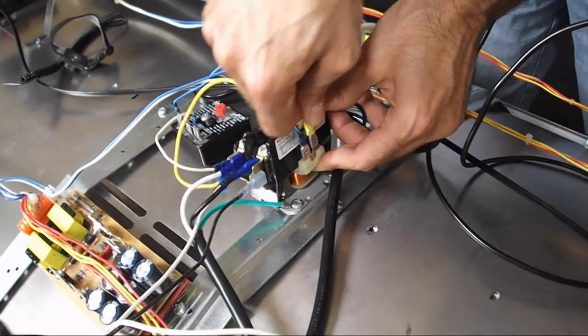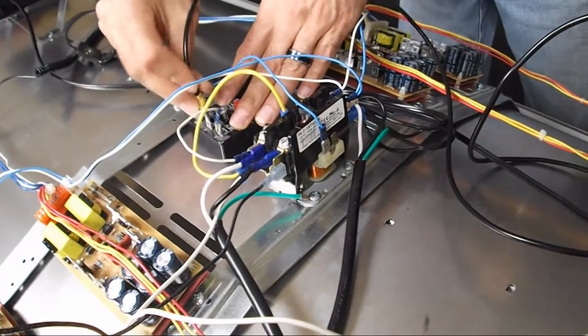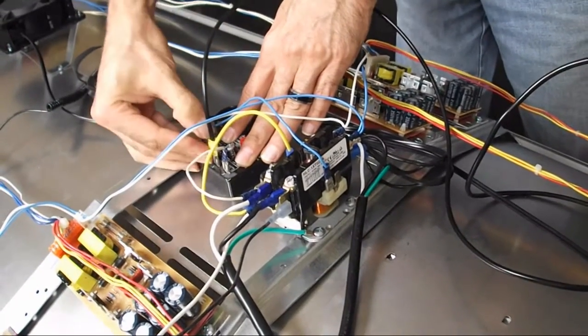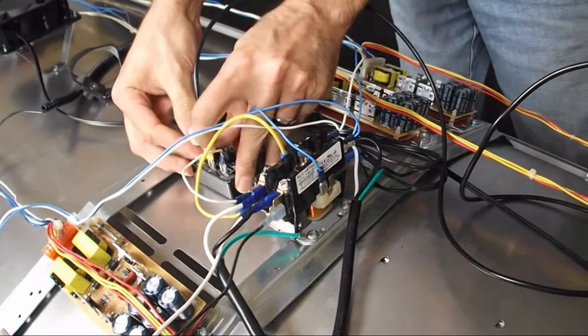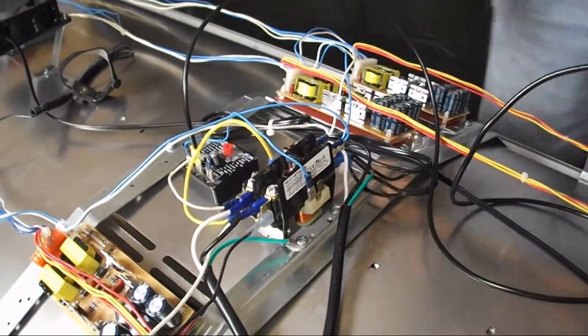So, since we do have the backup timer, I'm going to actually connect it onto the appropriate terminal, A1 or 1. Some of the older ones were A1, and the newer ones are 1, and the universal ones have both markings on there like that.